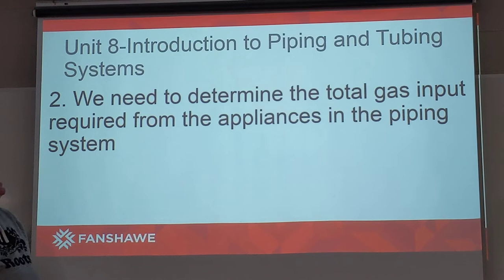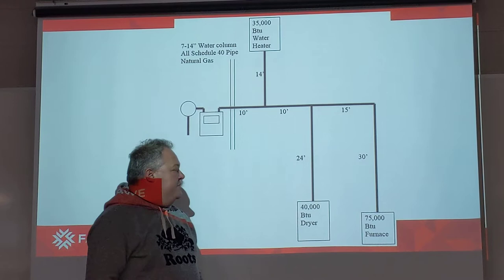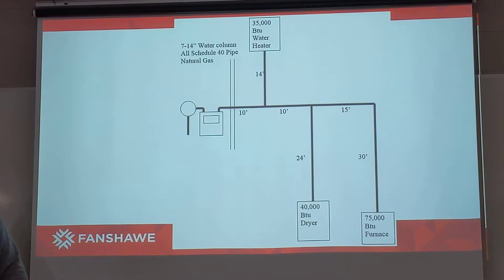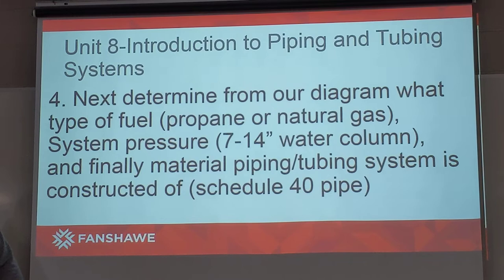Step number two, we need to determine the total gas input required from the appliances in the piping system. Going back to our diagram, we add up all the BTU requirements: a 35,000 BTU water heater, a 40,000 BTU dryer, and a 75,000 BTU furnace, for a total of 150,000 BTUs. To summarize, step number three: our LMR is 65 feet and our total gas load is 150,000 BTUs. Because we're in between table values, we're going to go to 70 feet, which we'll talk about in a second.